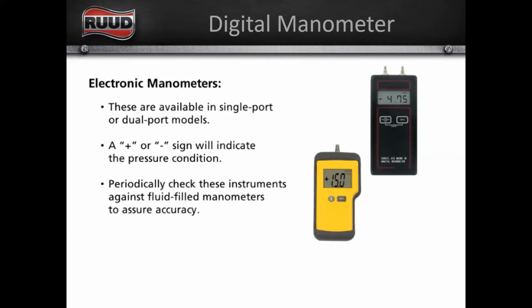It doesn't really matter though, whether it's positive or negative, because when we go to add those numbers together to get our total static, we're going to throw those signs away. But yeah, if it's on the return side, it's going to be a negative static. And depending on what device you use to read it, it might put a little minus up there. It might not. But technically it's always going to be a negative number. Your supply is always going to be a positive number, because remember the slide that I showed towards the beginning of your air handler, with your negative side on the return and your positive side on the supply. That's the same thing that we're looking at, right? We're creating that pressure differential. So yeah, the return's always going to be negative, but it might not show as a negative depending on what tool you're using. But if it's on the return side, it's a negative.